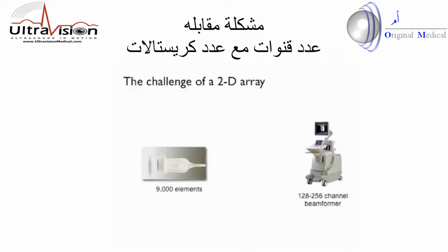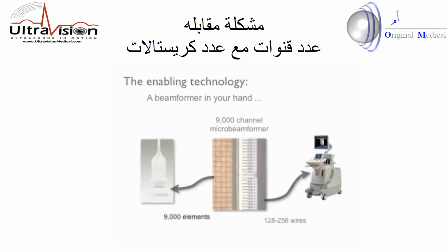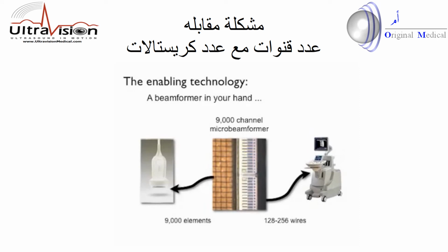Transducer that constitutes this advance, because even if you've got a 9,000 element transducer, how are you going to connect it to an ultrasound machine? You can't make a cable with 9,000 wires inside it. And really the enabling technology that has allowed this development to take place is that of the beamformer, the 9,000 channel beamformer, which is not in the ultrasound system but in the probe itself.